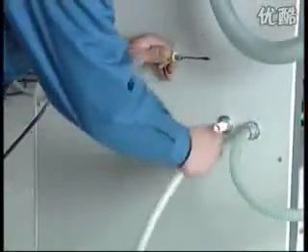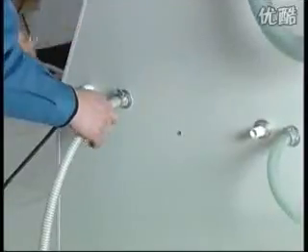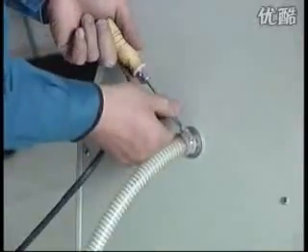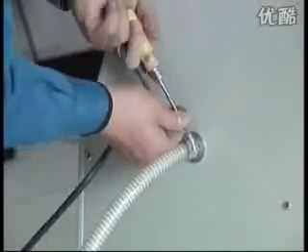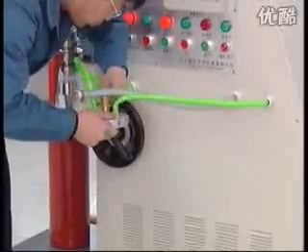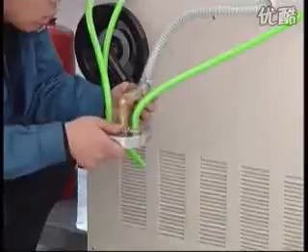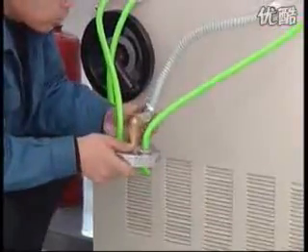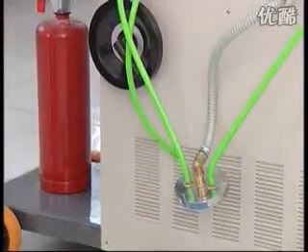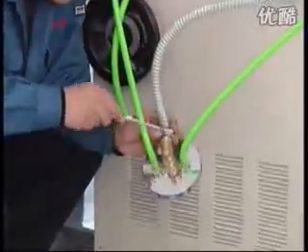Procedure for filling 35 kg and other large capacity fire extinguishers: connect the powder source pipe with the 35 kg powder suction inlet. Take out the 1 to 8 kg powder suction pipe. Change to the 35 kg powder suction pipe and pressurize. Tighten the fastener, pressurize, then start filling.